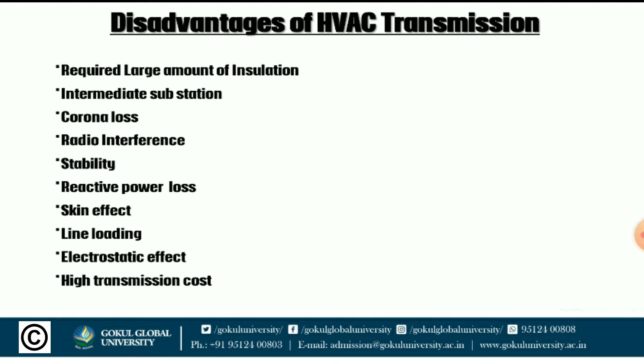Now is line loading. The loading on the HVAC transmission system is limited to one-third of the thermal rating of the conductor due to the transient stability and the line reactance. Now, electrostatic effect. The HVAC transmission system generates the electrostatic effect, which is very dangerous to human beings. The last one is the high transmission cost. It means the transmission cost increases with increase in transmission voltage. This is because as the transmission voltage increases, the cost of the transformer, switchgear and other equipment also increases.